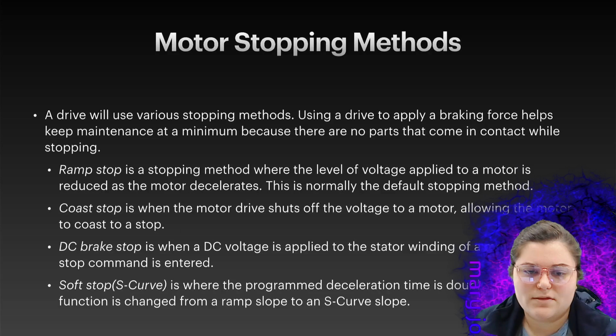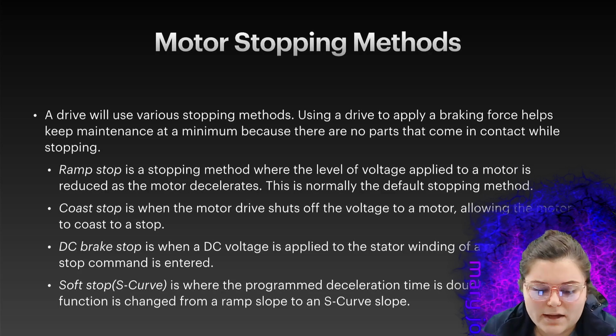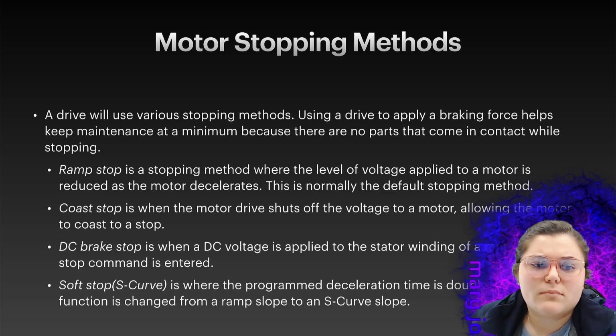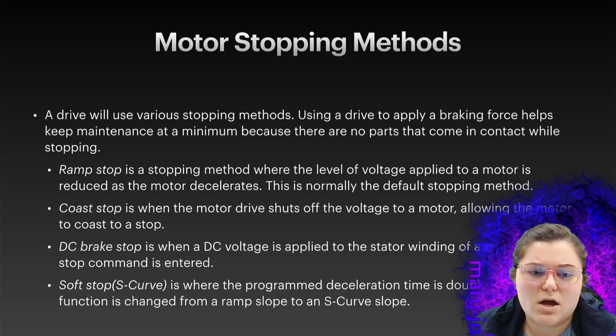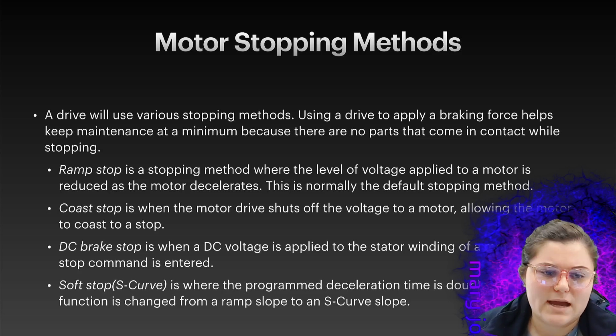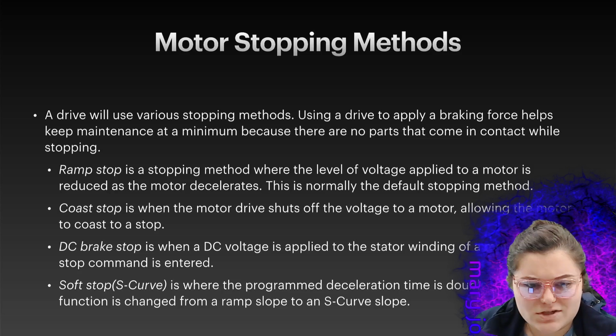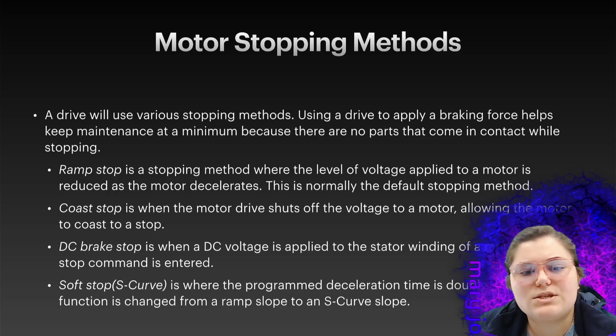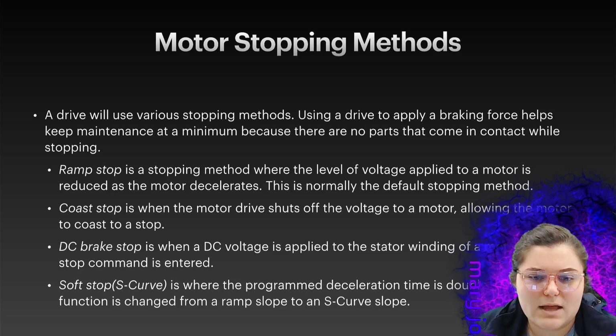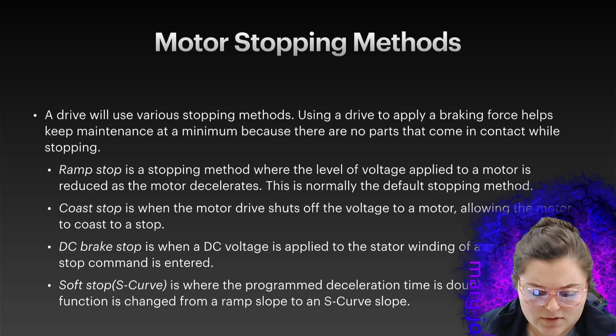And motor stopping methods. We've been over this in a past chapter, but just to touch back on these, a drive is going to use various stopping methods. Using a drive to apply a braking force helps keep maintenance at a minimum because there are no parts that come in contact while stopping. So going over just the four most common is ramp stop, and that's a stopping method where the level of voltage applied to a motor is reduced as the motor decelerates. This is normally the default stopping method, so that is what would normally be set as the stopping method straight from the factory. So that's factory settings.